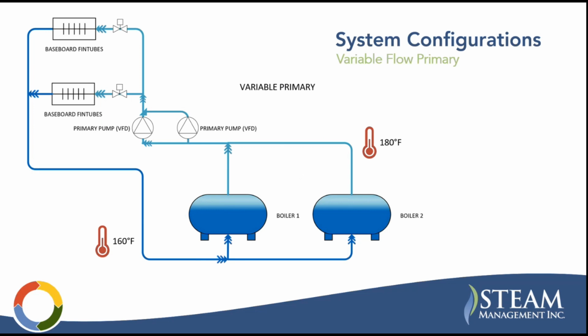This is a variable flow primary system. So basically kind of the same idea, but your primary pumps are on VFDs and you pump out to the system and back through the boiler. So your system pumps are also your primary pumps that pump through the boiler. This is a recommended configuration for new condensing boiler installations, which we'll talk about later.